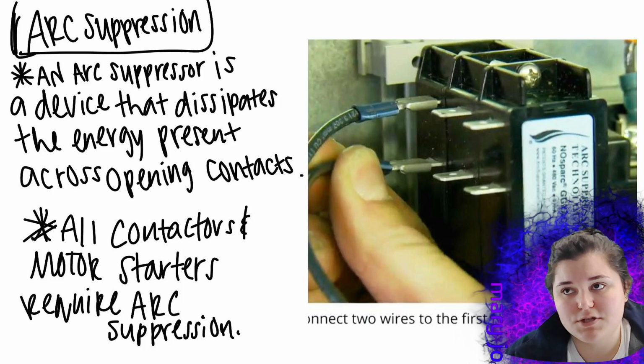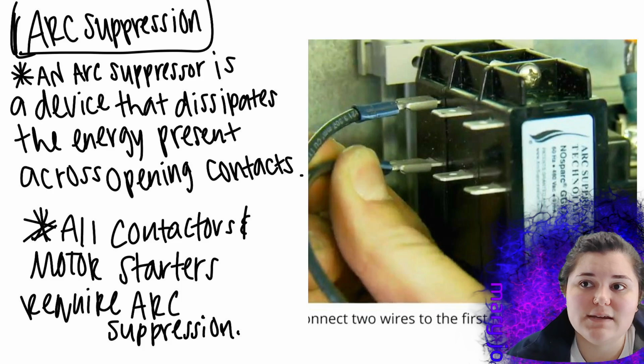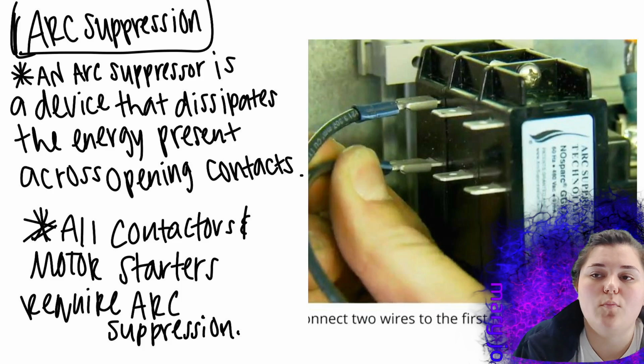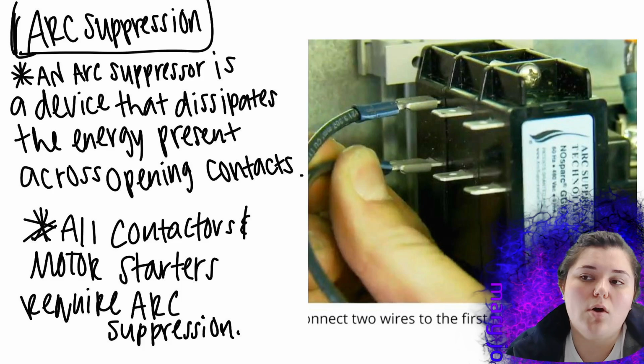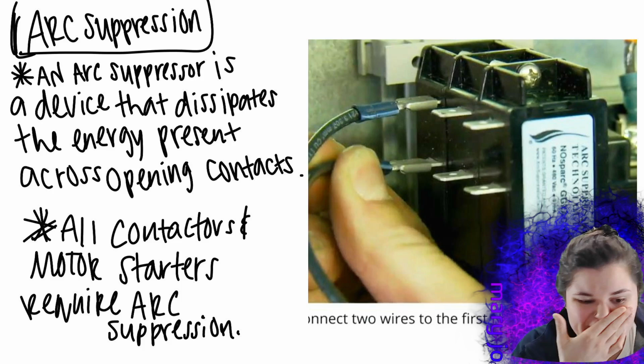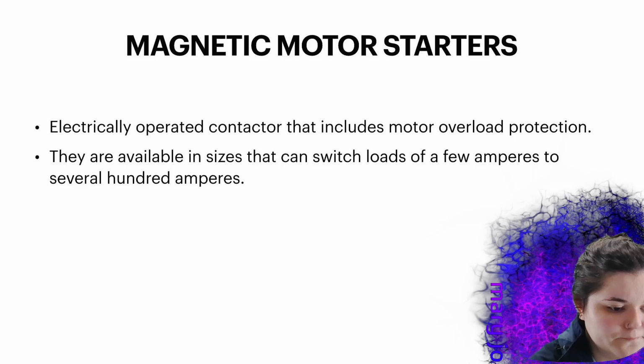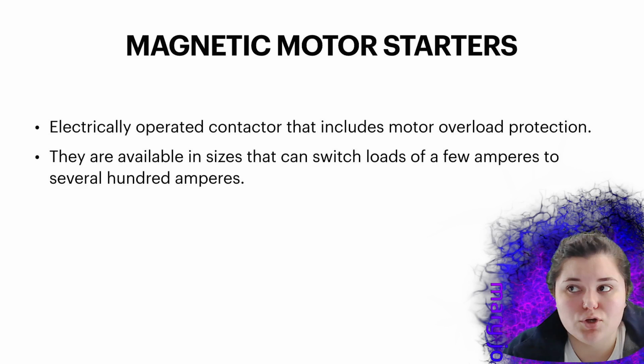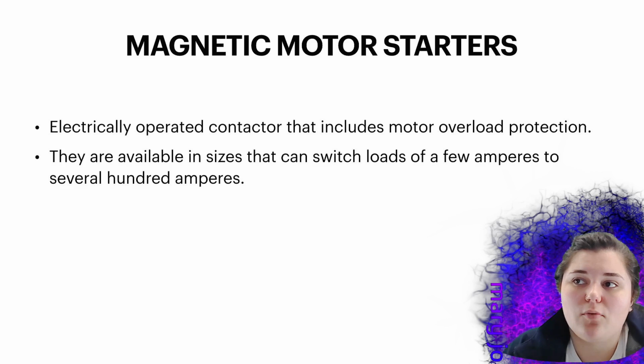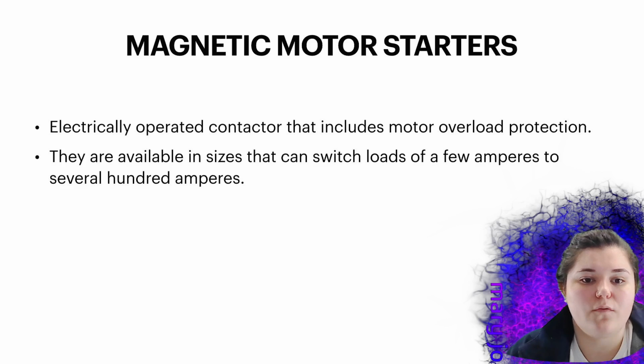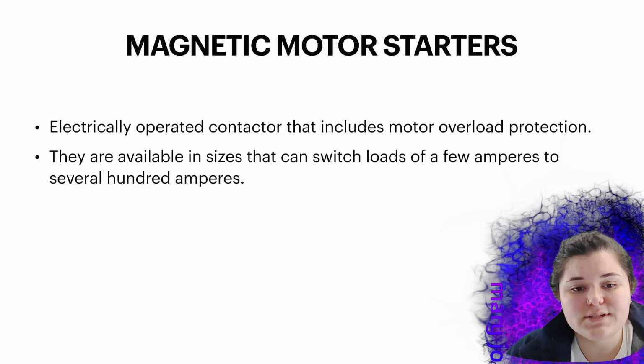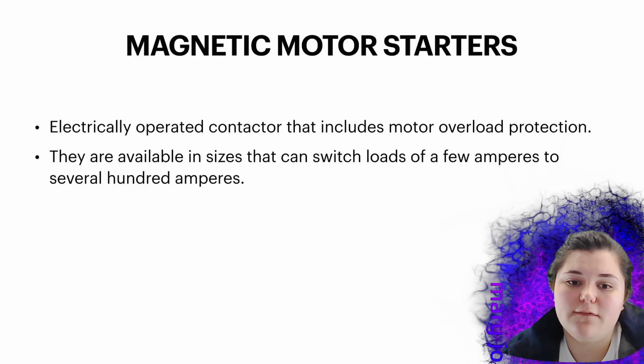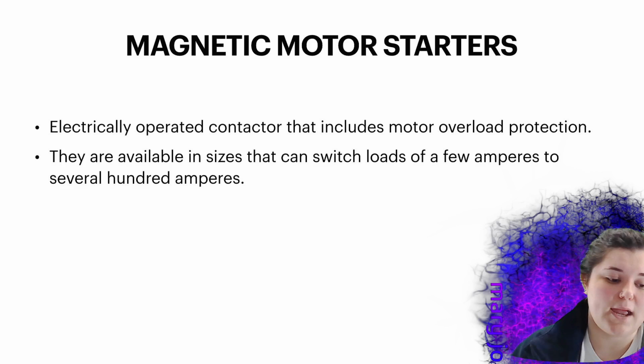Arc suppression. An arc suppressor is a device that dissipates the energy present across opening contacts. All contactors and motor starters require arc suppression. Magnetic motor starters. Electrically operated contactor that includes motor overload protection. They are available in sizes that can switch loads of a few amperes to several hundred amps.